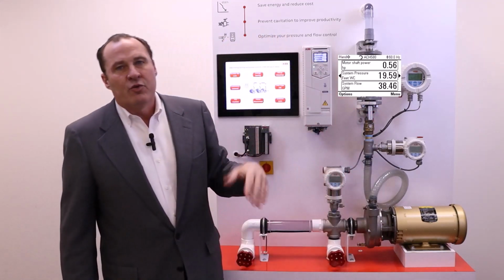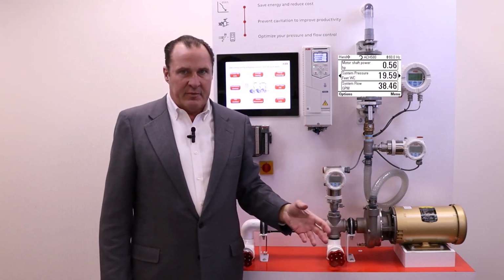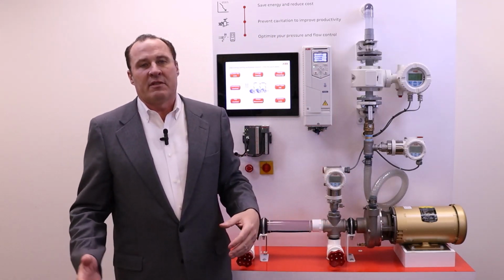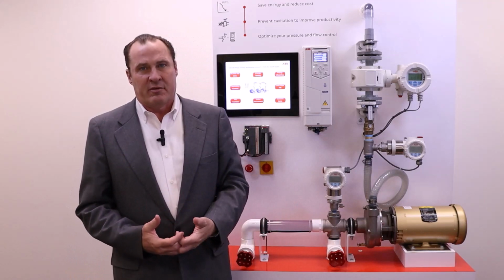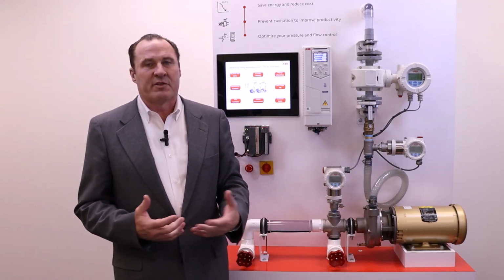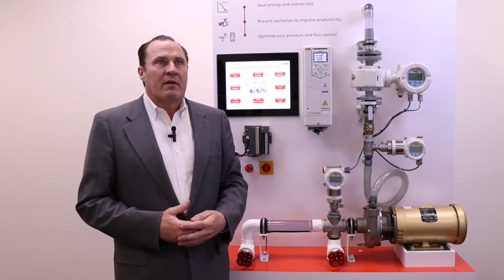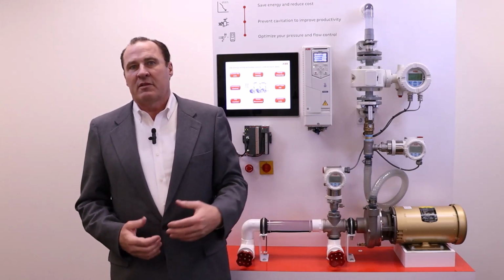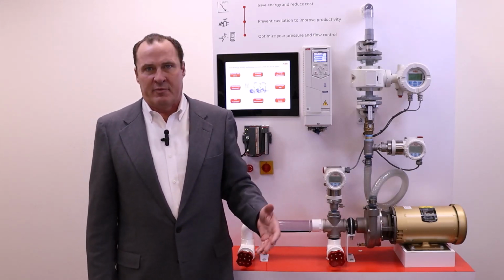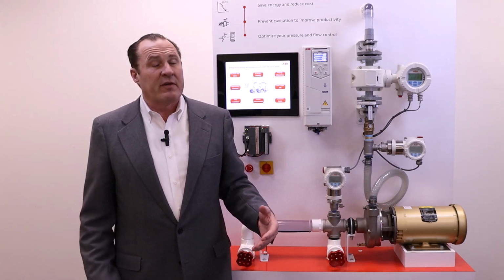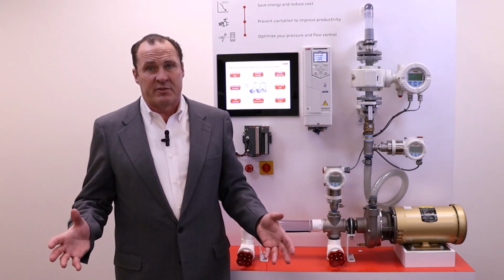Now, you could do this with 5 data points. You do need to have the first data point at 0 gallons per minute. Okay, so 0 flow. If you do it with 5 data points, the system won't be as accurate as 10 data points. So you've got between 5 and 10 data points you can enter into the drive.